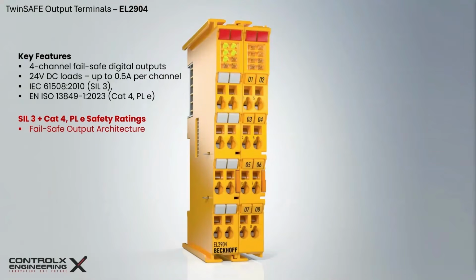Each of the 4 outputs is a fail-safe output, meaning the output is designed so that any internal fault forces it into a safe state, which is the off state. The terminal performs continuous self-monitoring to detect dangerous failures. This is a core requirement for SIL 3. The EL2904 continuously measures the output current on each channel. This allows it to detect short circuits, cross circuits between channels, load faults, and output driver failures. If the measured current does not match the expected behavior, the terminal forces a safe shutdown.